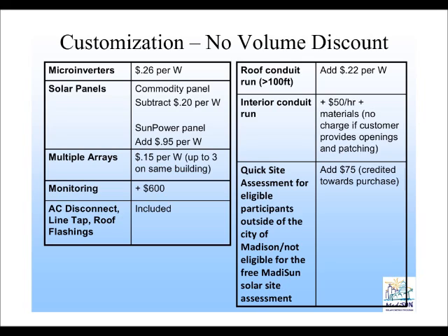To counteract that, a few years ago, a new kind of inverter was invented. Instead of having one large central inverter, it makes a small cigar-box-sized inverter that goes on the back of each panel. Each panel has its own mini — they're so small they call them microinverters. The output from each panel can then be converted into AC separately, and if one panel has a reduced output because of temporary shading from a tree branch or a telephone pole, only that module is affected. The other panels have their own microinverters and are unaffected, and this can make a dramatic increase in efficiency on a complicated roof with chimneys or dormers that cast partial shade during the day. Microinverters can help greatly to minimize the effect of that.